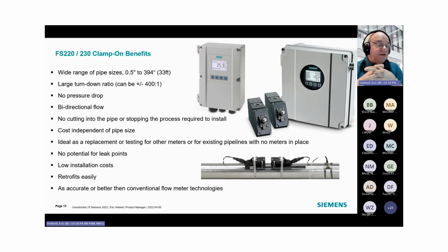If you want to put these into an existing system, for example, you may have a mag flow meter in line, but you want to have an ability to double check the magnetic flow meter. You can put one of these right next to the magnetic flow meter and have a check system. So just in case the mag meter goes down, you're still measuring flow and still correcting flow. All right, good question. Okay, I'm going to take a pause.